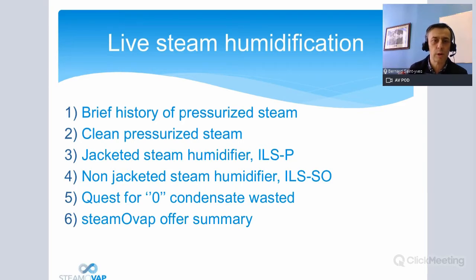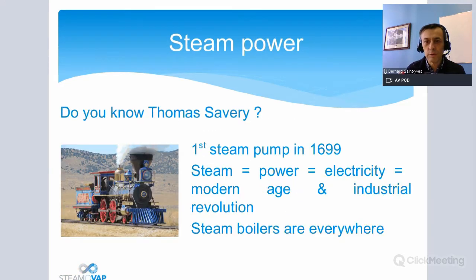Make a brief history of the pressurized steam. Talked about the clean pressurized steam that is now available, and that's a new trend. And the jacketed steam humidifier, which we call ILSP, P for pre-heating chamber, and non-jacketed steam humidifier, which we call the ILS-SO. Then the quest for the zero condensate wasted that had been launched a few years ago by some of our competitors. And then we will end with just a quick summary of our offer on the pressurized steam humidification.